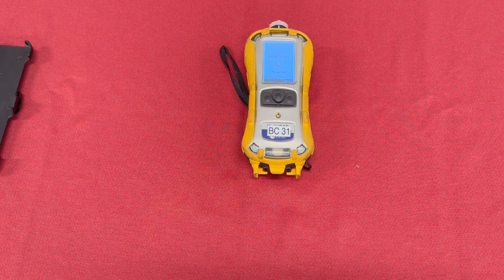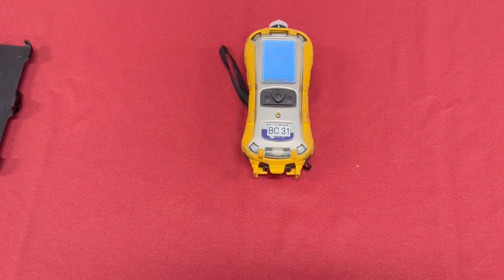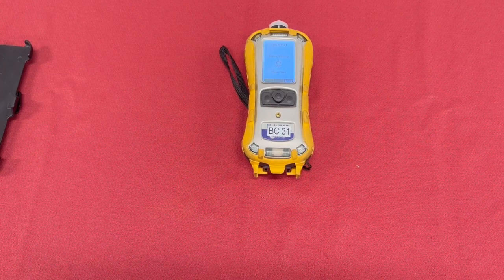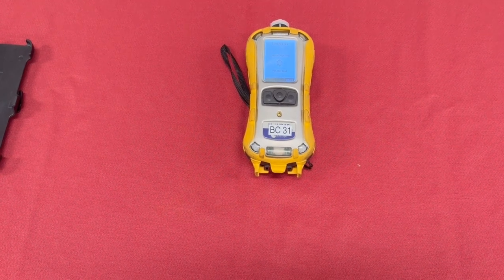What we're going to do today, we're going to talk about calibration and bump testing, but we're actually going to do a calibration. The bump test is conducted exactly the same, except it's a shorter thing. And we'll talk about the difference of calibration and bump testing while we're doing some of this and we have some time to get through. This warm-up process, as it's taking place now, you'll see it's warming up and it goes through all the sensors that are in it.